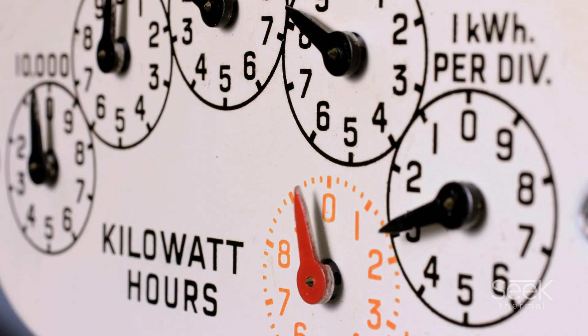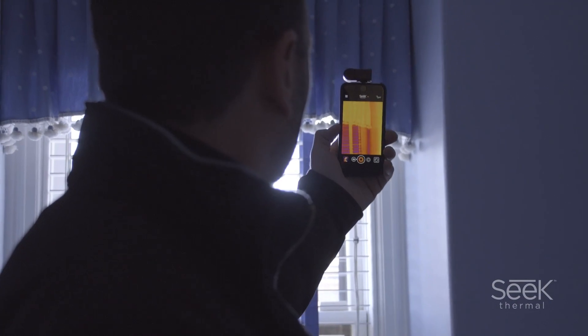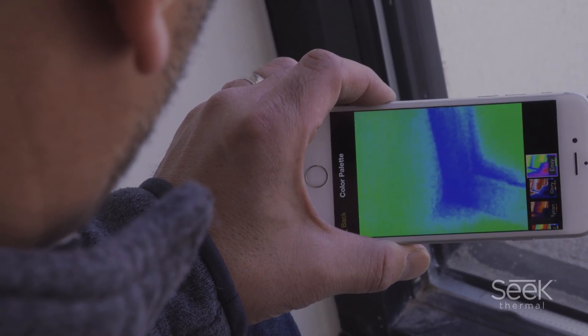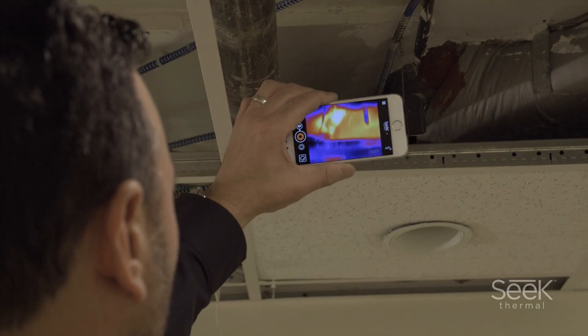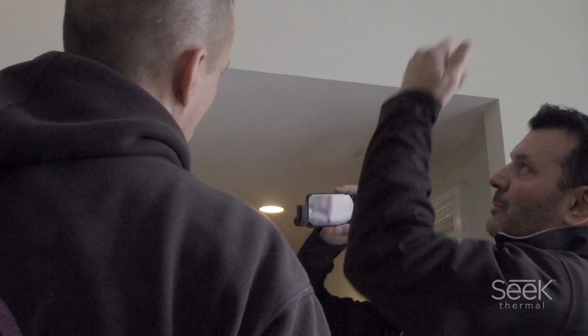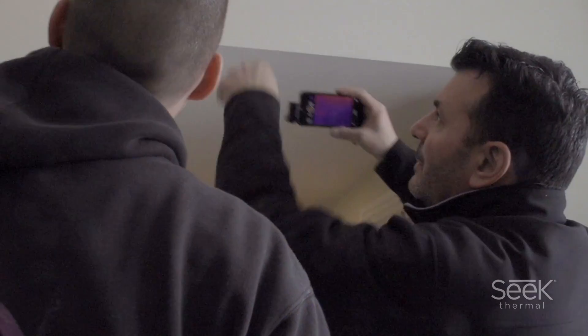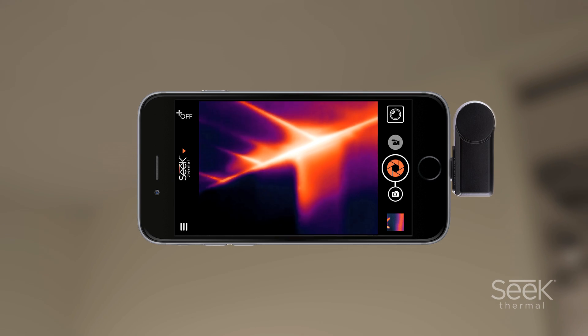In our state, the cost of electricity has increased for many residents by about 36 percent over this past year, so now more than ever our clients are calling us to participate in solutions that truly answer the requirement of solving energy loss or building envelope related issues. We've got an energy code requiring a certain performance level — a machine might be dumping 1,000 CFM but by the time we get to the other side it's 200 CFM. We want to know where that 800 CFM has been lost, and we can trace with the camera where it's dumping out.